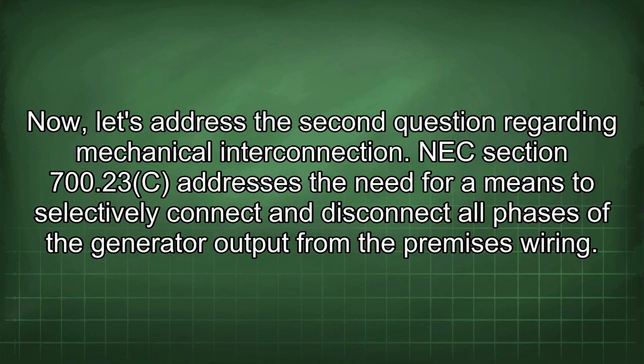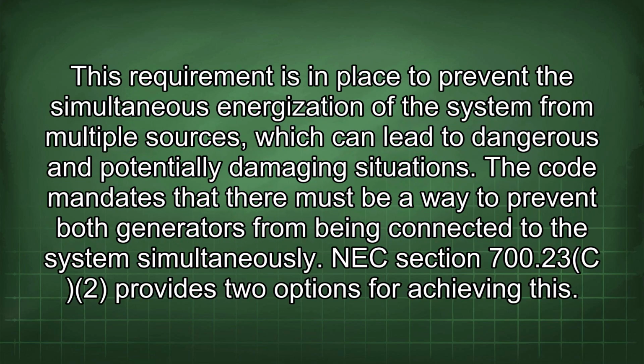Now let's address the second question regarding mechanical interconnection. NEC Section 700.23c addresses the need for a means to selectively connect and disconnect all phases of the generator output from the premises wiring. This requirement is in place to prevent the simultaneous energization of the system from multiple sources, which can lead to dangerous and potentially damaging situations. The code mandates that there must be a way to prevent both generators from being connected to the system simultaneously.